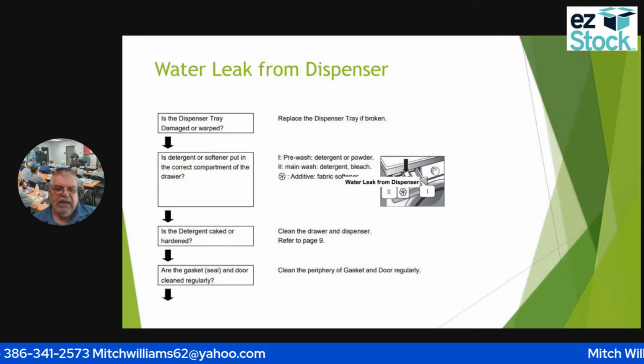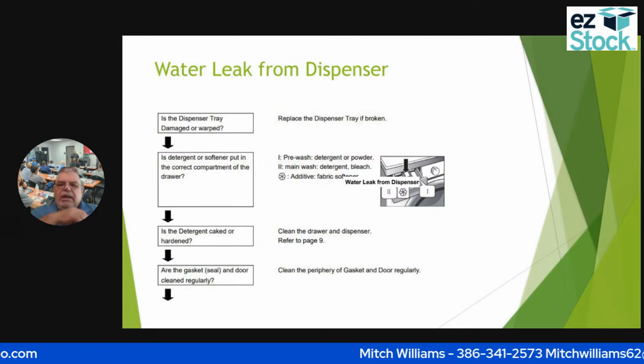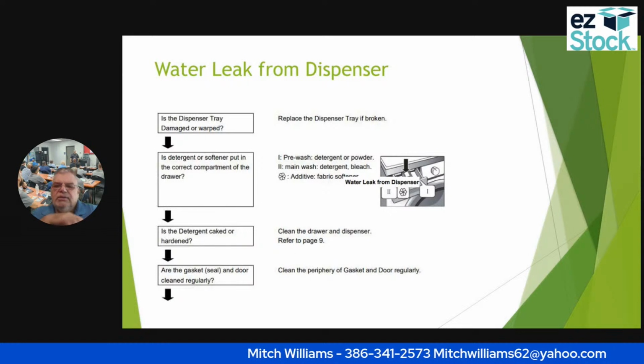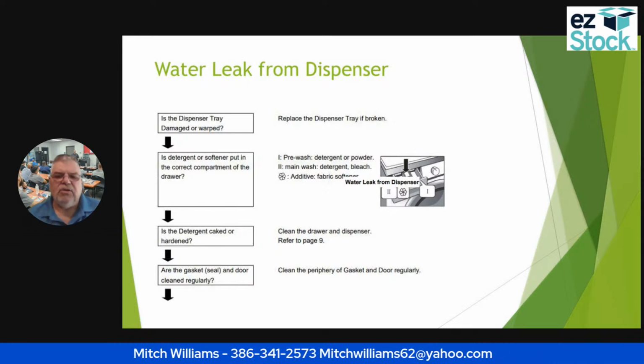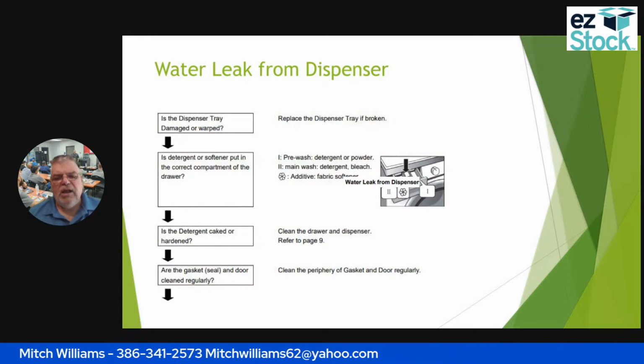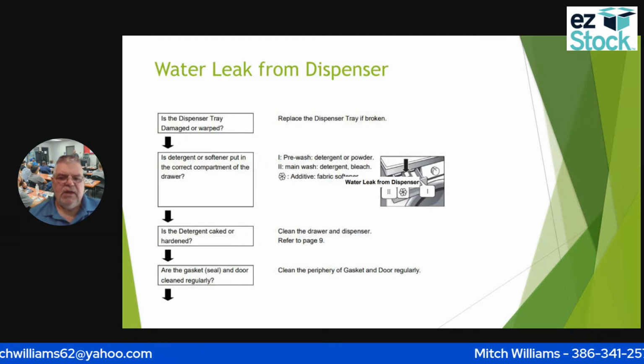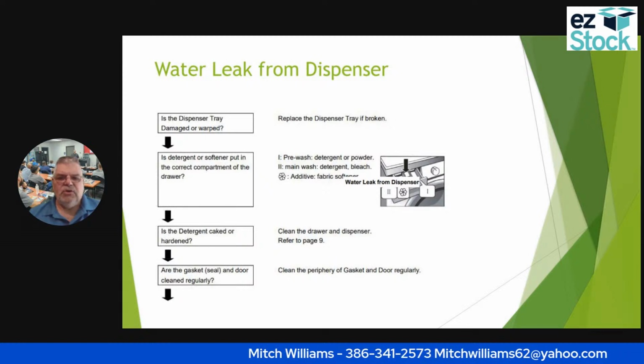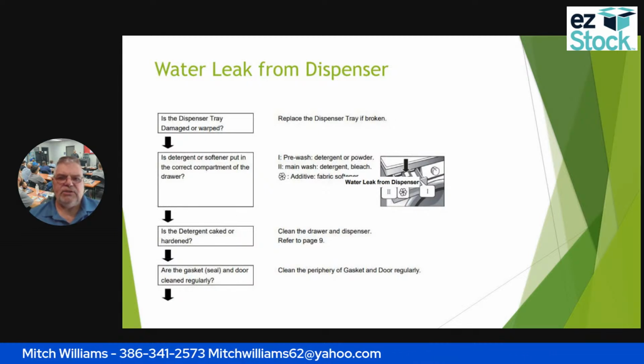Are the gasket seal and the door cleaned properly? And if not, how often? Whenever you pull it out, you can look at it and see. If not, I can always clean it and tell the customer that this is something that they need to be doing, or else you're going to be back and you'll have to be charging them $85. I don't know what you guys charge for a 15-minute job.